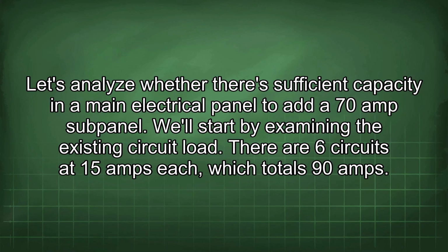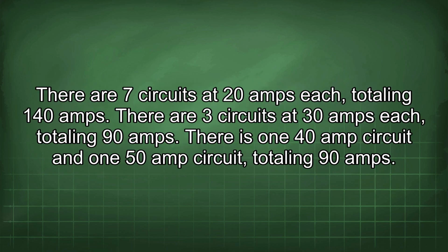Let's analyze whether there's sufficient capacity in a main electrical panel to add a 70 amp subpanel. We'll start by examining the existing circuit load. There are 6 circuits at 15 amps each, which totals 90 amps. There are 7 circuits at 20 amps each, totaling 140 amps. There are 3 circuits at 30 amps each, totaling 90 amps.